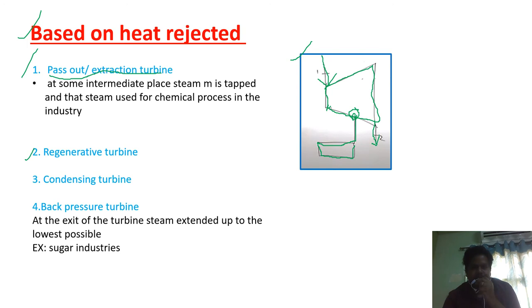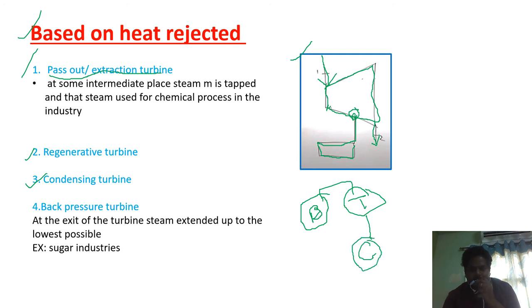The next type is the regenerative turbine, which we already discussed. The other type is the condensing turbine — this is the regular Rankine cycle. In the Rankine cycle, from the boiler steam enters the turbine, from the turbine it goes to the condenser, from the condenser to the pump, and from the pump back to the boiler. Since after expanding through the turbine the steam goes to the condenser, this type is called a condensing turbine.